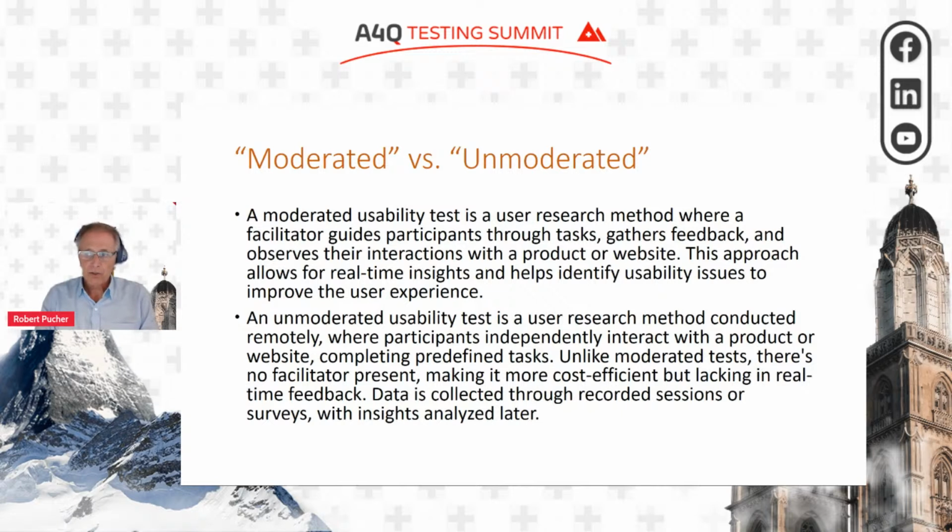This was a so-called moderated usability test. Moderated usability test means that the usability test is guided by a person. In that case, it was me, which is very often helpful. Unmoderated tests, which are also done, the user just gets a sheet of paper or a computer screen, and they're told what she or he has to do and go through the test. I'm not a fan of unmoderated tests. They are relatively cheap. You can use them in several settings, but usually moderated usability tests are a lot better.